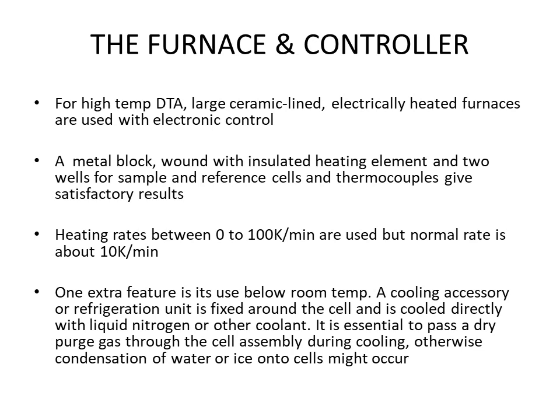The furnace is a metal block wound with an insulated heating element, with two wells — one for sample and one for reference — and together there is a thermocouple sensor. To give satisfactory results, heating rates are maintained between 0 to 100 Kelvin per minute, with a normal rate of about 10 Kelvin per minute. If operating below room temperature, a cooling accessory or refrigeration unit is fixed around the cell and cooled with liquid nitrogen or other coolant. A dry purge gas must be passed through the cell assembly during cooling to prevent condensation of water or ice onto the cell.